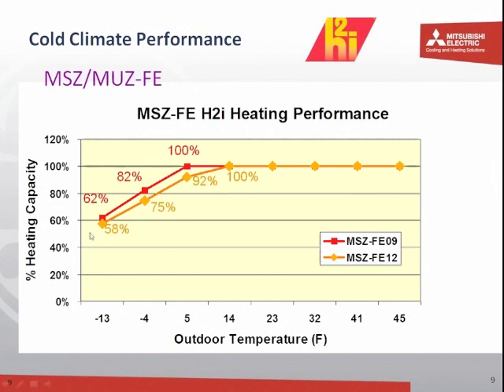As the temperature drops further and further outdoors, as low as negative 13 degrees, it's still producing heat. It's doing it at a highly efficient level, and it's doing it with all of the other features of the mini split, with active management of the indoor airflow, etc. Part of the sizing process is making sure that even at that low temperature condition, there's still adequate heat for the space. And that's part of what we're going to talk about at the end of the session, is how we determine that that is in fact the case. But in the three designs that have so far used this product, even in the worst case condition and even at the reduced amount of heat output, it's been sufficient without the need for supplemental electric heat of any kind in the construction.